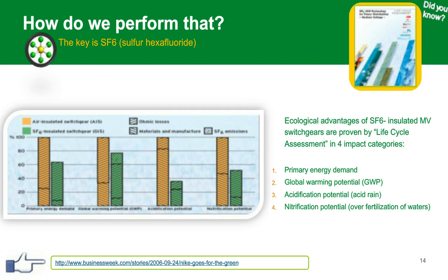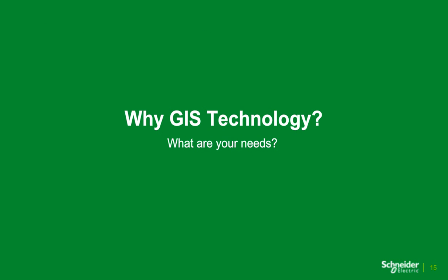Phil, we do have a couple questions in regards to the gas. Sure, yeah. One question, it's a two-part question. Why must gas be under higher than ambient pressure? It actually doesn't necessarily have to be, but it commonly is because as you pressurize the gas, you have better insulation. It insulates better than non-pressurized gas inside the tank, and so that allows us to get things even more compact. In other cases, people will pressurize gas to increase BIL rating or some other electrical ratings in the switchgear. Great, thank you.